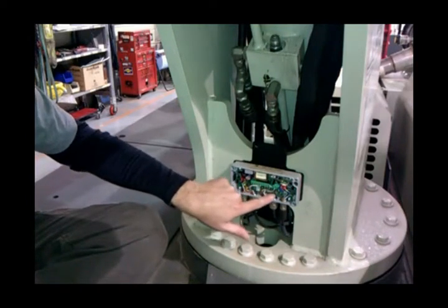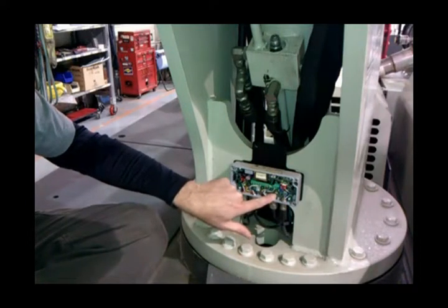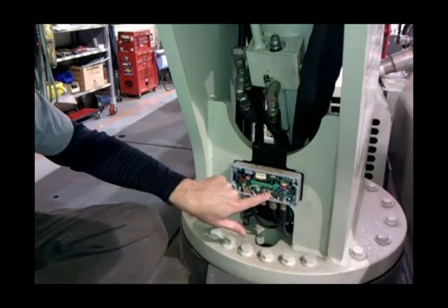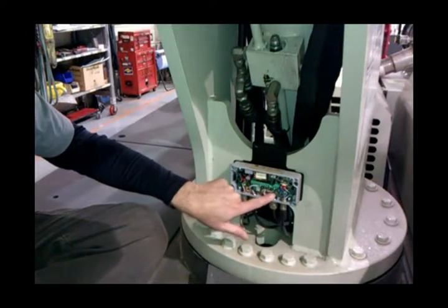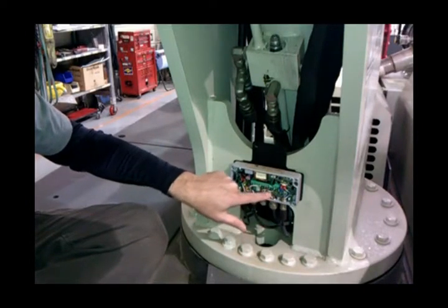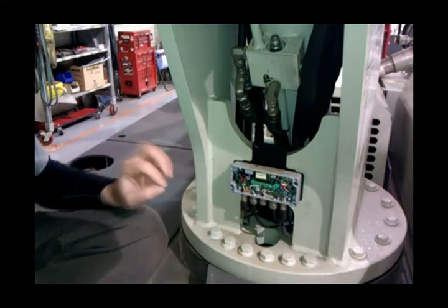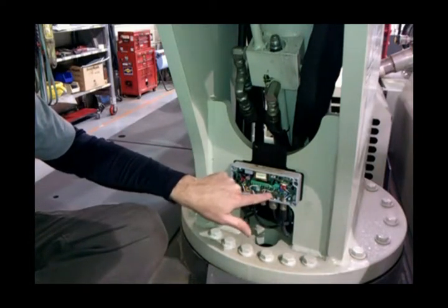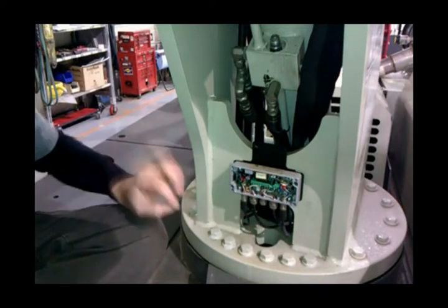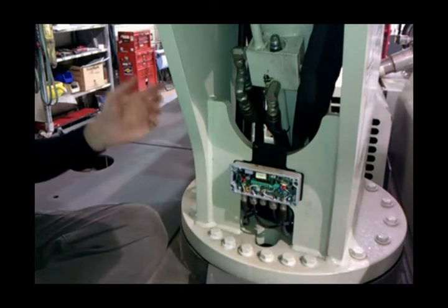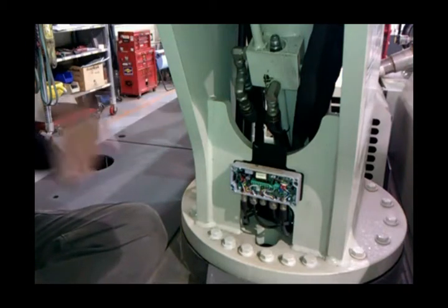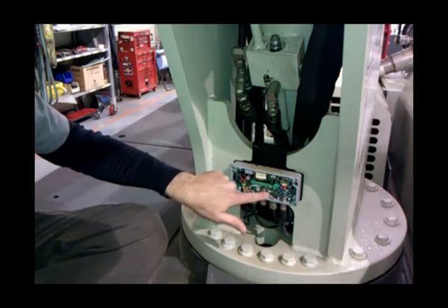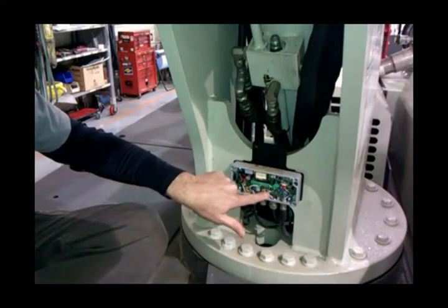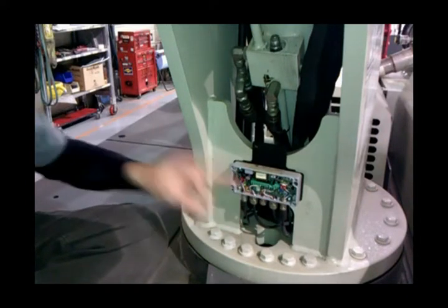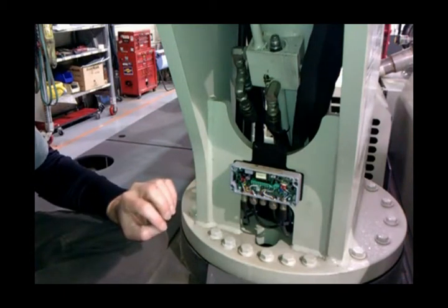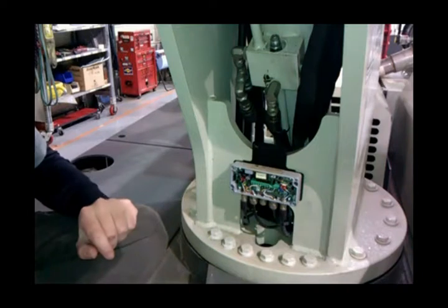What you need to know is where these two objects are right here. This little silver object, there's two of them. One is for your calibration of the bore, and the other is for the calibration of the rod. There's a little switch sticking down on the bottom of them, and when we span the sensor, these switches need to be thrown for the sensor that you are spanning. So after you've done the 0 of your bore transducer, you're going to do a span of the bore transducer. In order to span it, you push this button on the left-hand little silver switch to the right, and that will give you the correct value in order to do the span of the bore transducer.